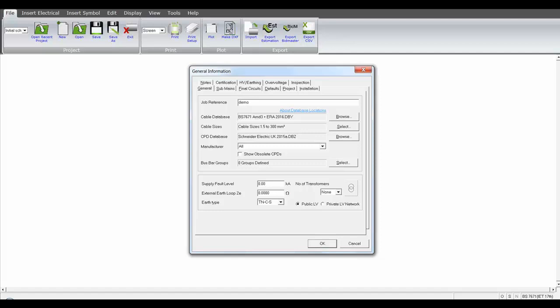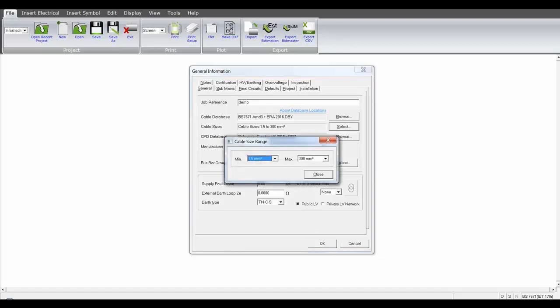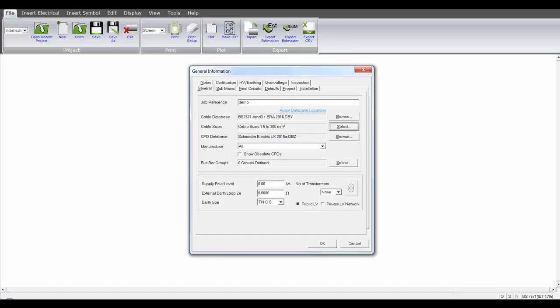First of all, we have our cable database, currently to the 17th edition Amendment 3, soon to be changing to the 18th. Cable sizes, where you can set the goalposts on the cable sizes. You may have bending radius issues and you might want to impose maximum and minimum cable sizes. This means the software will automatically parallel up if the load is sufficient to increase the cable. So you might end up with smaller cables paralleled up, which you can control automatically.